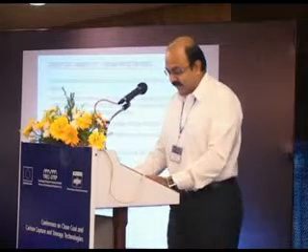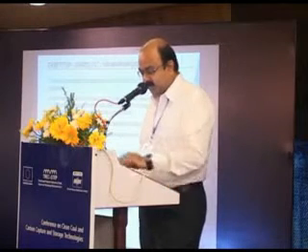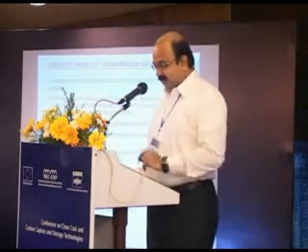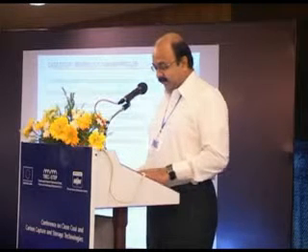The PLF was very low, I think less than 70%. I remember 70% was okay on the economizer part that is mentioned there. Frequent tube failures in the economizer band. They would stop the unit, cut that portion, and then restart. So the availability was going down and sinking.